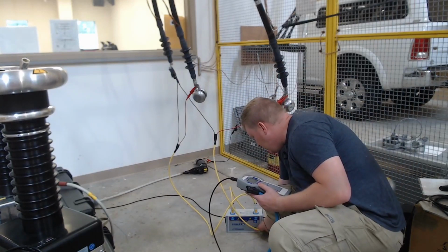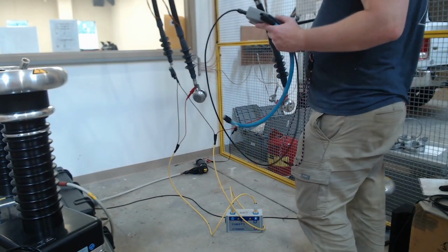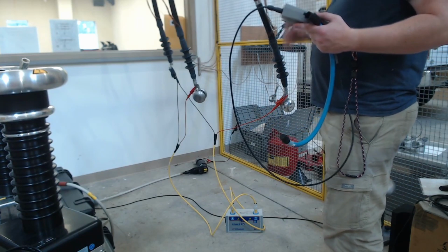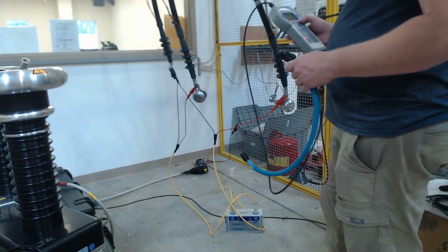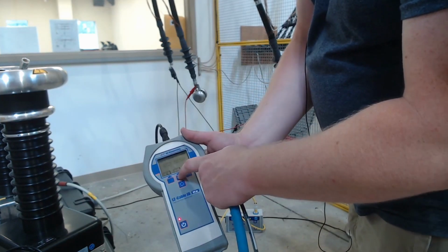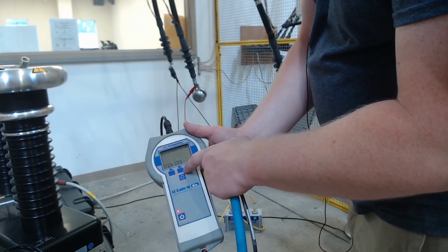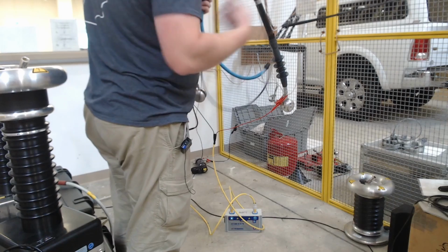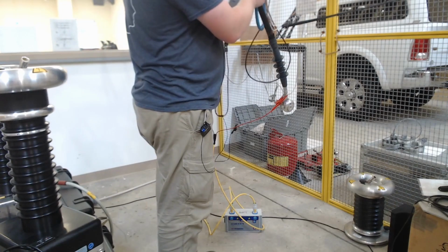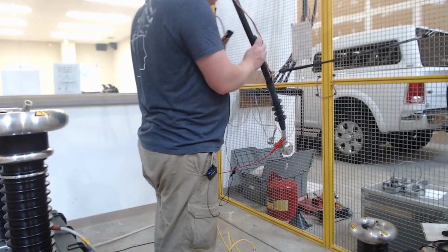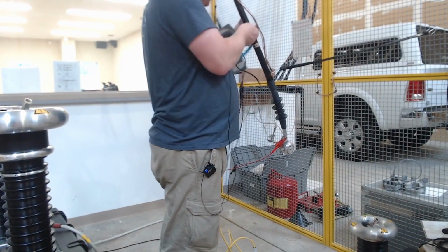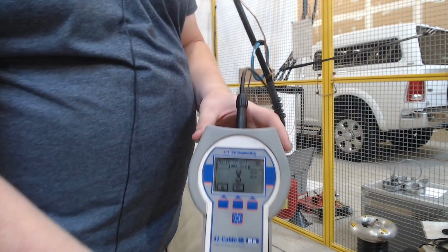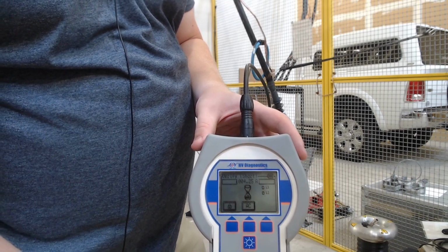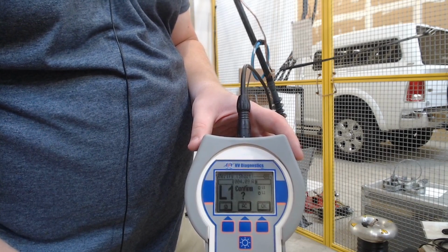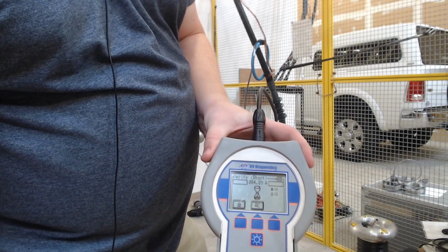So we have our L1 hooked up to our A phase and C phase, and then L2 is hooked up to our B phase and C phase, so then C is going to be our return for all of our signals. So now we're going to ID. We're going to do new. We're going to do short. And so now we're going to verify short. So we're going to come over to our A phase. We're going to keep our coil over our shielded section because our cable is still shielded here. We're going to have it point away from our transmitter. So our arrow is pointed away. So it should come up with L1. Yep, L1, okay, confirm. It's going to read again. It should give us an L1 with a check mark.